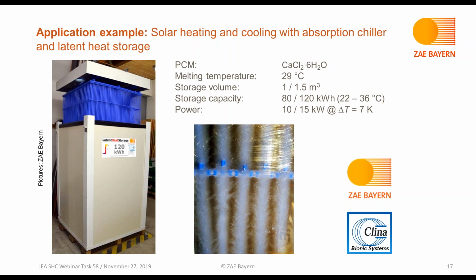So the special feature of this type of storage is we are using a so-called capillary heat exchanger, which is immersed in the liquid PCM. The blue capillary tubes are made from plastic to account for the corrosive properties of the salt hydrate. And the picture in the middle shows the PCM crystallizing on the surface of these capillary tubes.